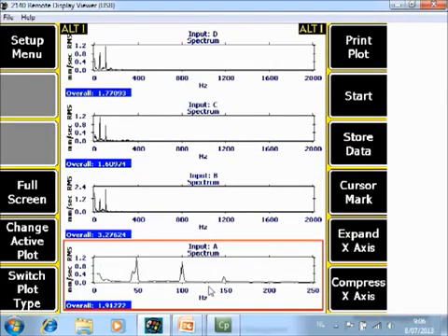So when I now expand the peak, you see here this was the imbalance value, but the imbalance value is not one peak now, but multiple peaks, because the speed changed during data collection and the amplitude of all those peaks is wrong. So more or less this spectrum is completely wrong.